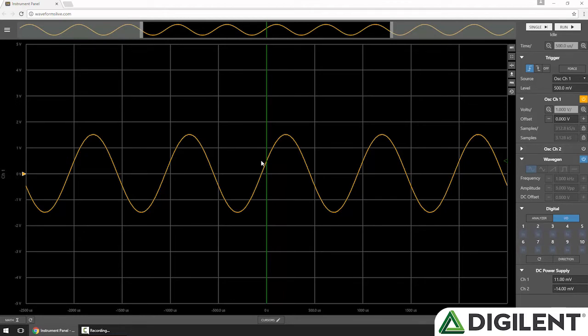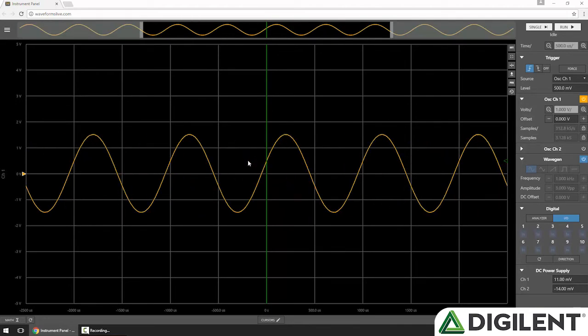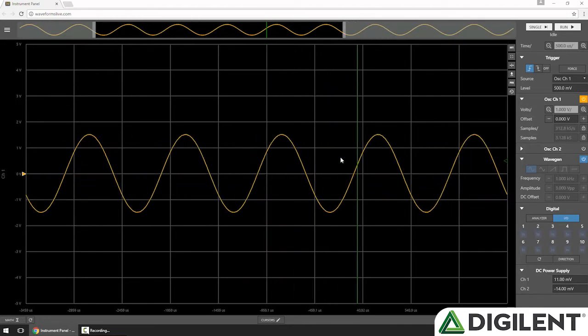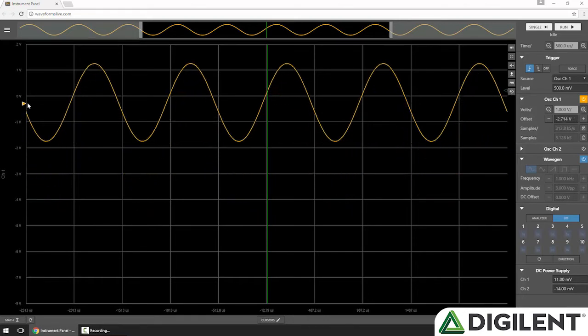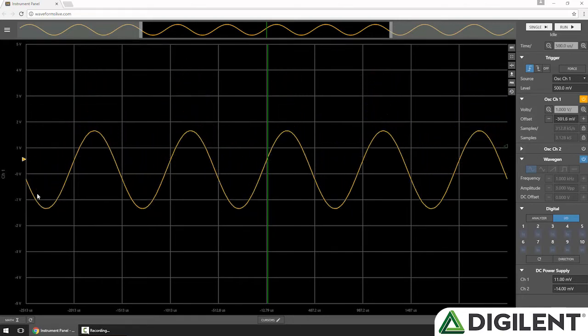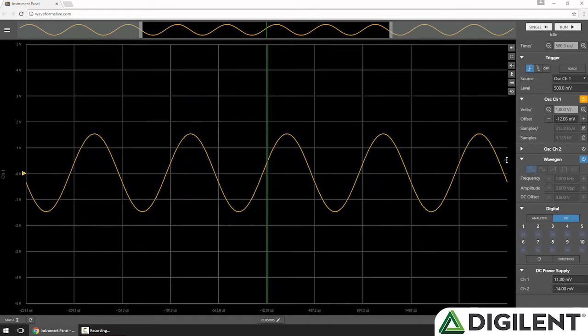I can manipulate the data in the chart by scrolling to zoom and clicking and dragging to pan. I could also do this using controls in the controls panel. I can grab the anchor to vertically offset a channel, and I can grab the trigger threshold anchor to manually set the trigger point.